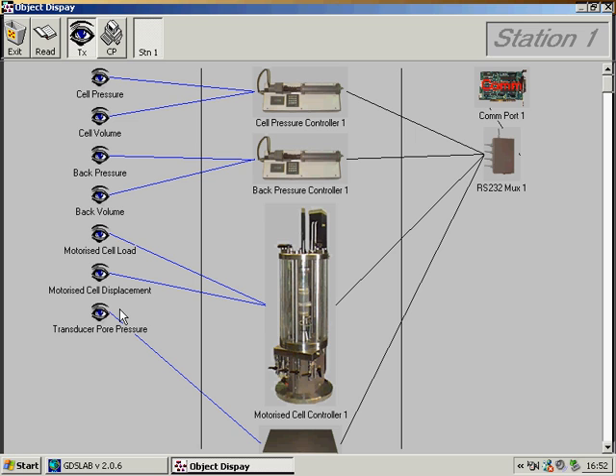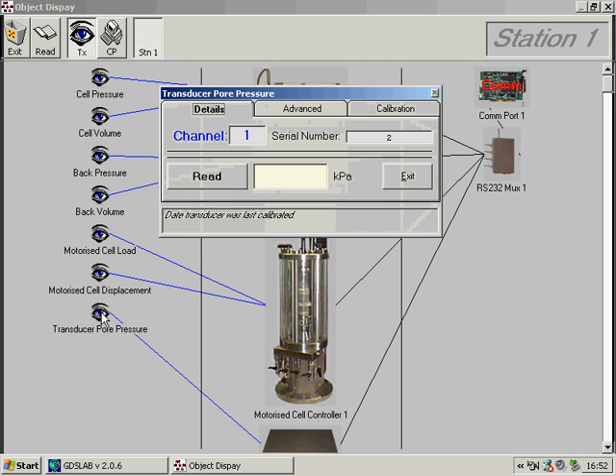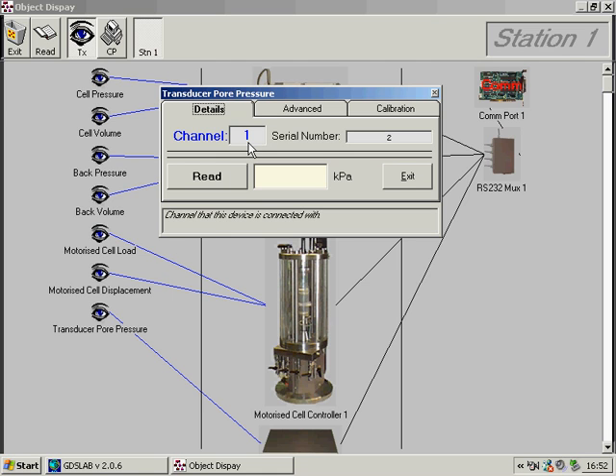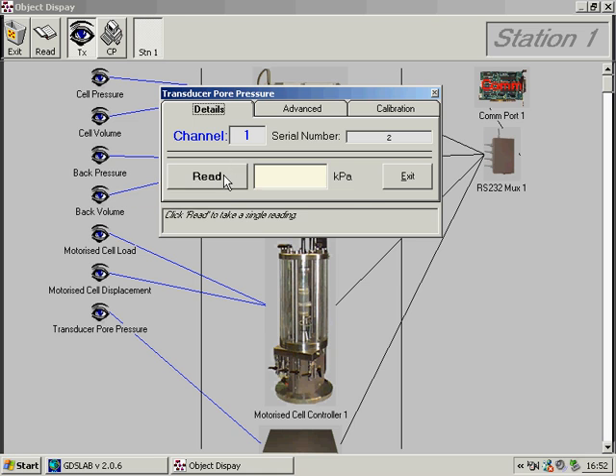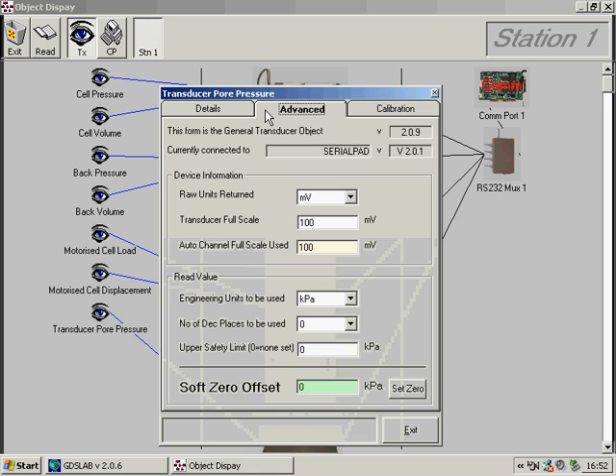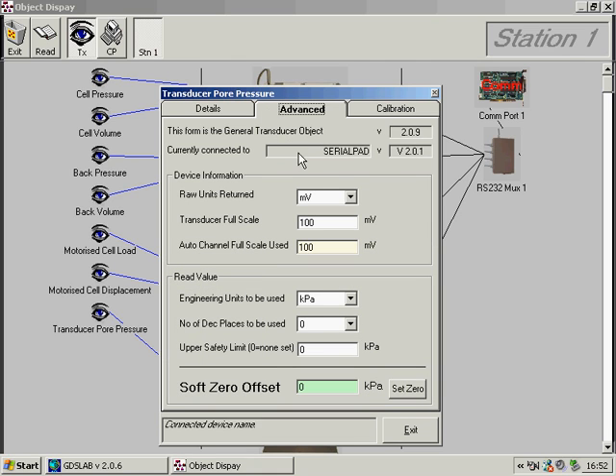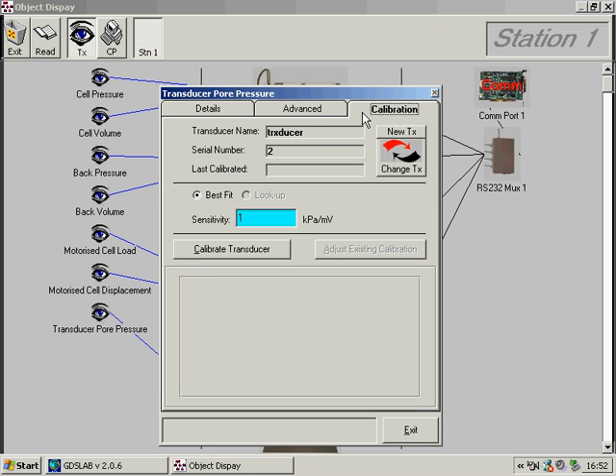The eye icon represents all the transducers set up in a particular station. For example, if I click on the pore pressure transducer connected to the serial pad, I can see that it is connected to the serial pad channel 1. I can take a reading of this. On the advanced tab, we set up all of the appropriate parameters for that transducer.